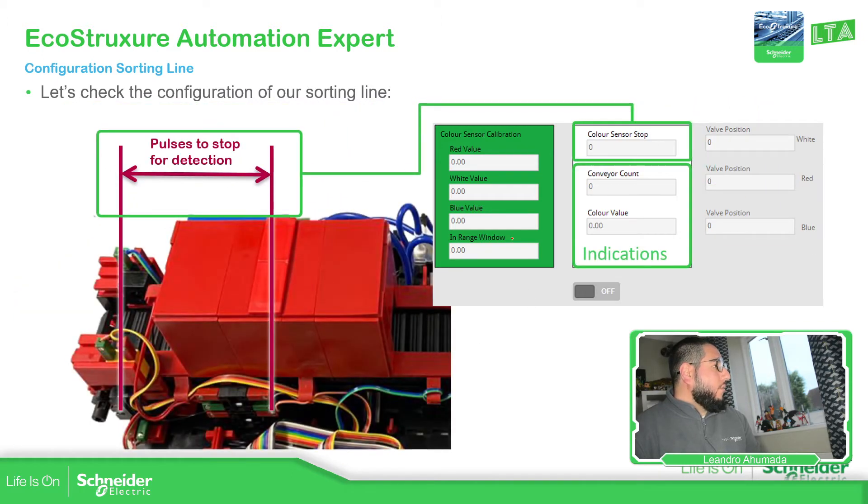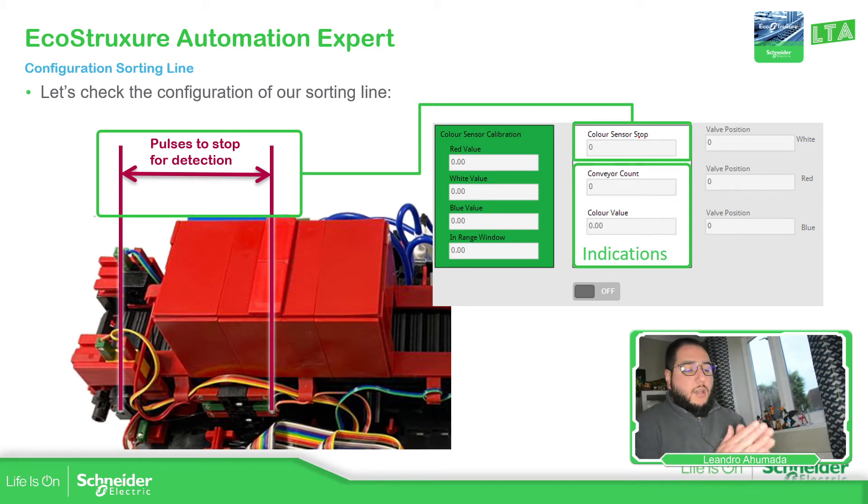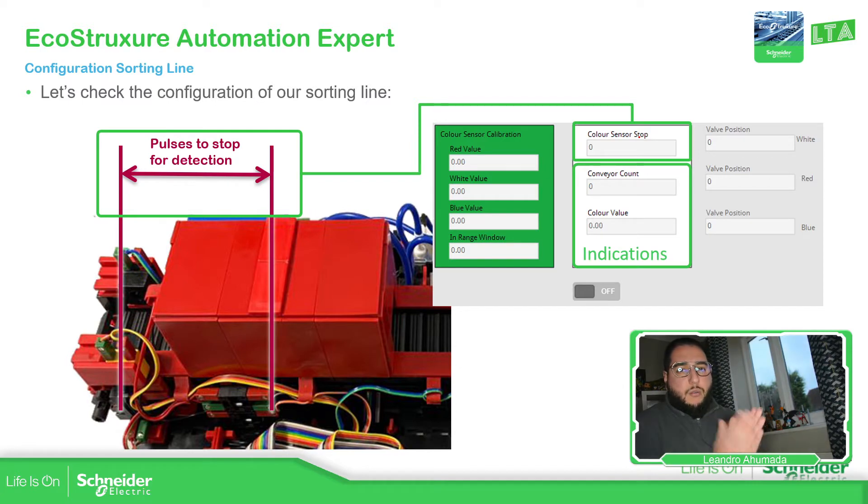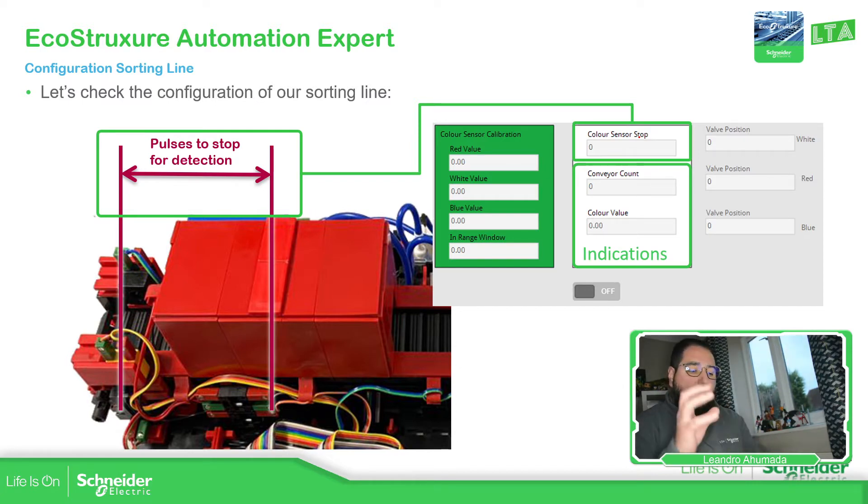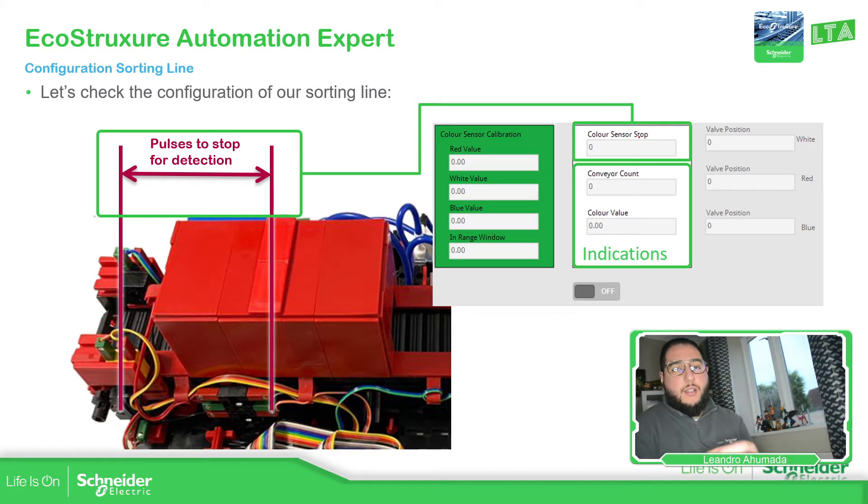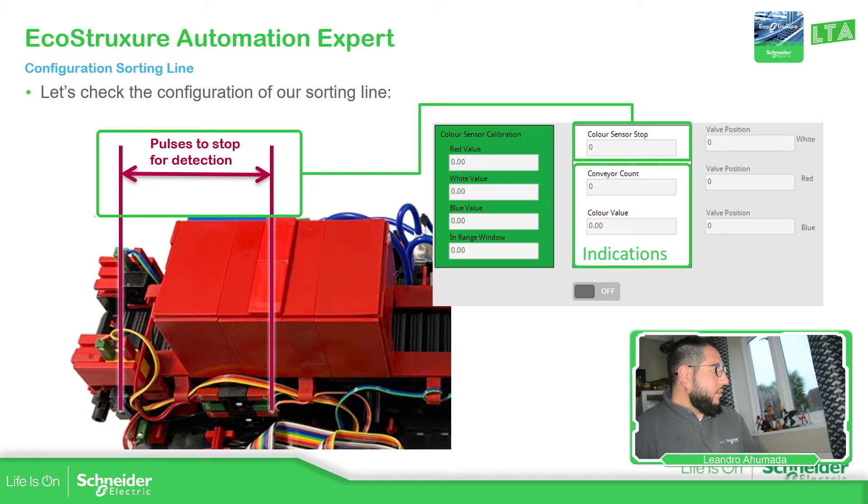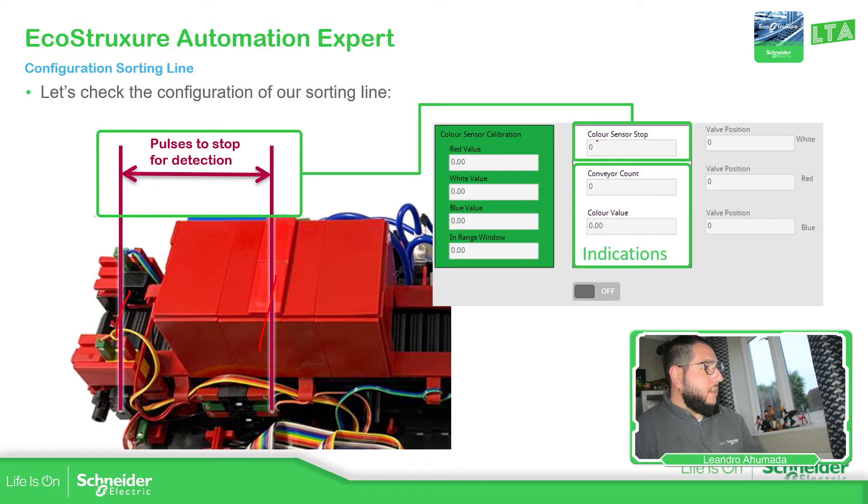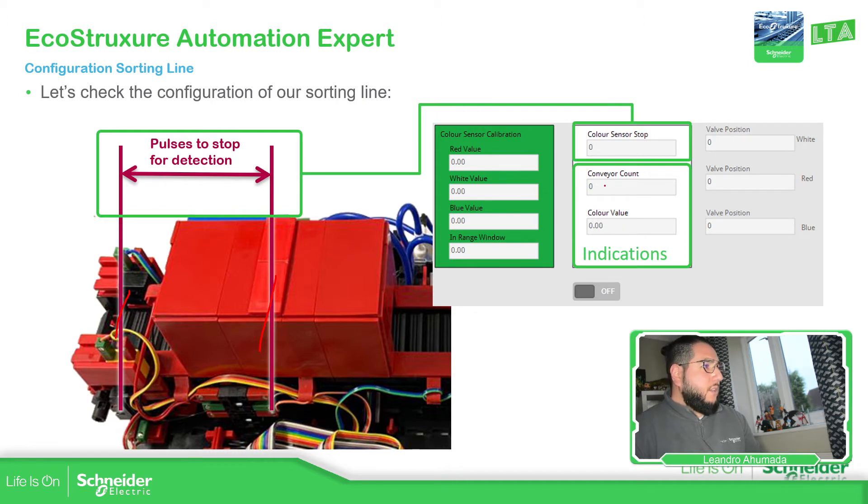Then what we need to configure in the second part, this box, is the sensor stop. That's the amount of pulses we require to make the conveyor stop so the sensor can detect the product and see which color it is. For that, we just need to count the pulses from here to here, and the value should be here. Then we have these two for indication so we can see the color value detected and the conveyor count.